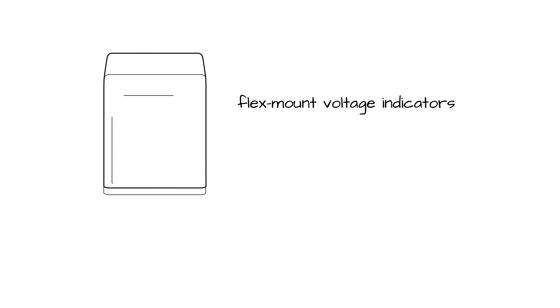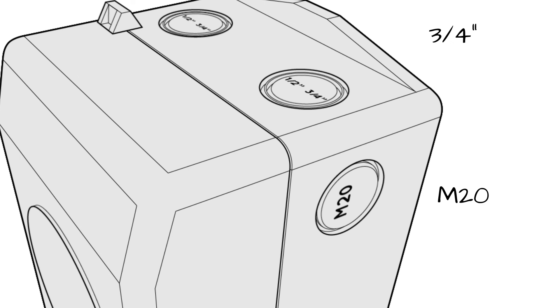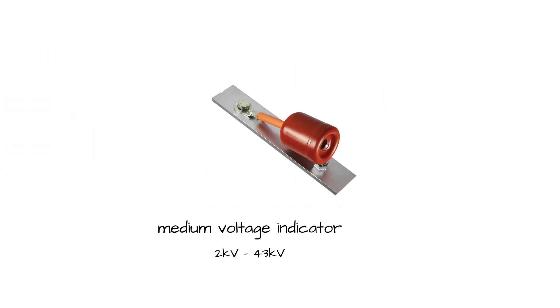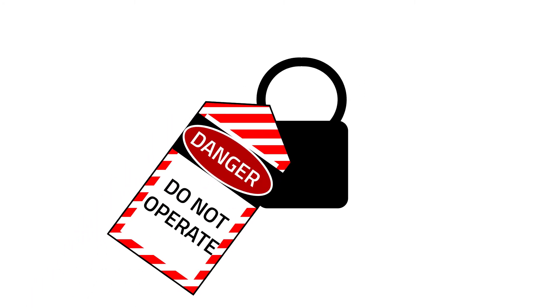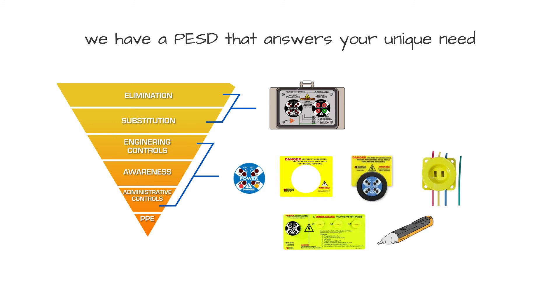Other PESD product variations include flex-mount voltage indicators that can mount onto any electrical enclosure with a ¾-inch or M20 conduit knockout, a fiber-optic voltage indicator for use in dead front bus panels with no voltage to the door, and a medium voltage indicator that can bolt directly to bus bars in 2 kV through 43 kV systems. No matter how simple or complex your lockout-tagout procedure is, we have a PESD that answers your unique need.